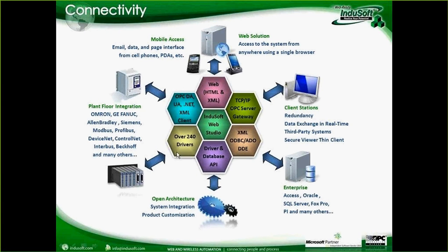If we don't happen to have the driver for the particular device that you want to communicate with, you can optionally use OPC to get to those devices. And we support many different OPC technologies. The OPC that many people are familiar with is OPC DA, which is OPC Data Access, and the OPC Foundation is now calling that OPC Classic. That has to run on a Windows PC because it uses COM and DCOM for the communication mechanism. That's an older Windows communications technology.